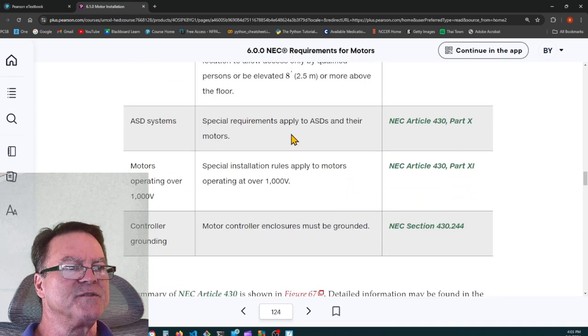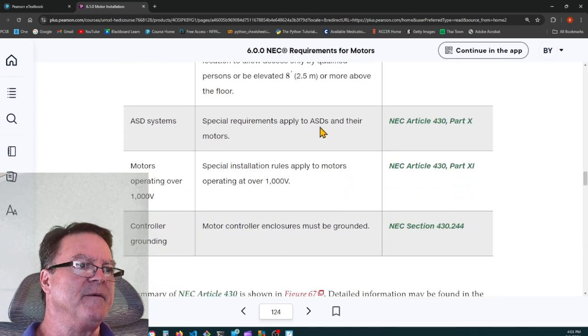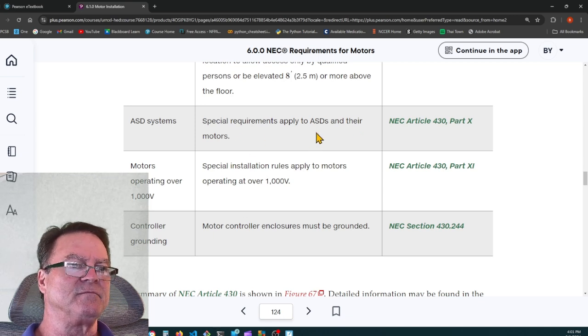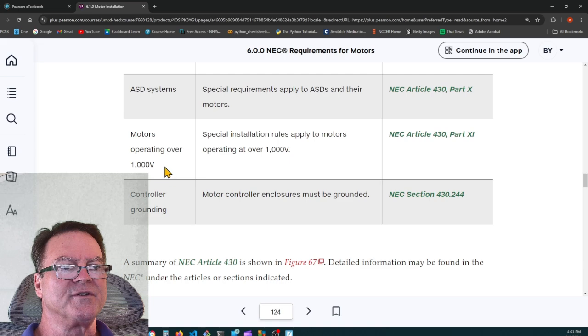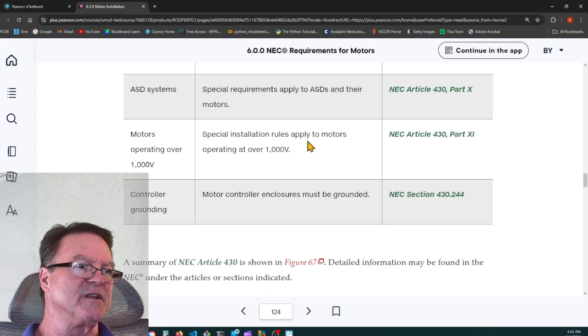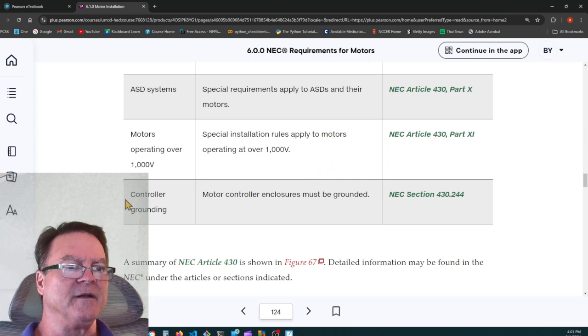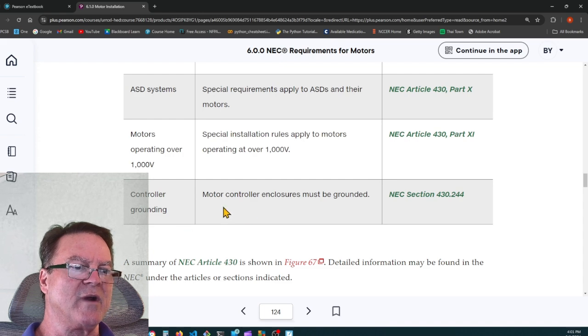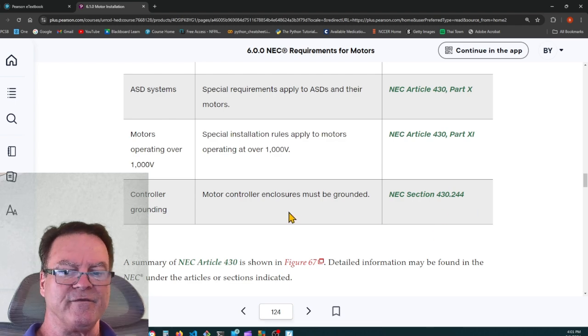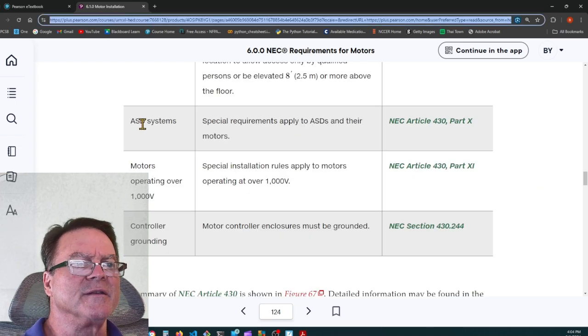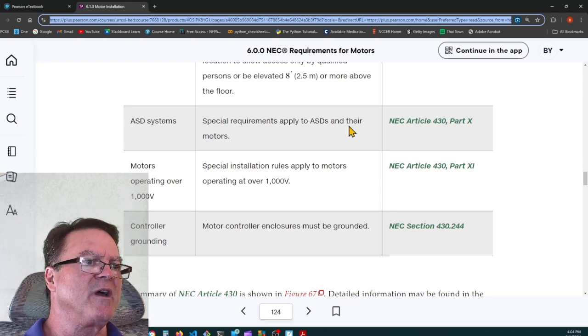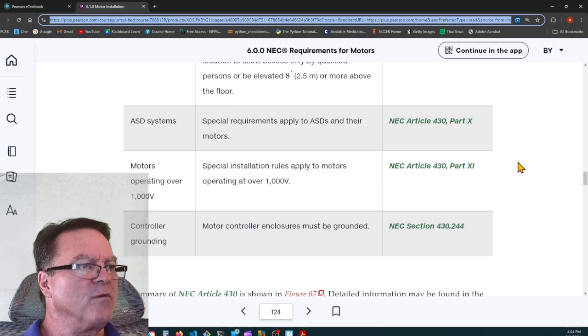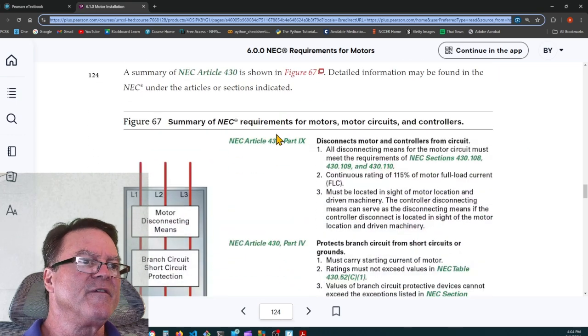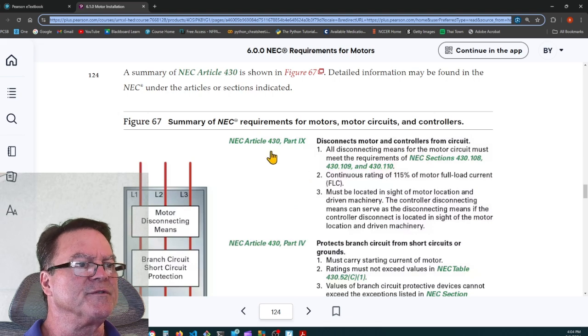above the floor. Special requirements apply to ASDs and their motors. Motors operating over 1000 volts: special installation rules apply to motors operating at over 1000 volts. And controller grounding: motor controller enclosures must be grounded. 430.244. All right, excuse me, yeah, that's adjustable speed drive. Special requirements apply for adjustable speed drives and their motors. That's 430 part 10. Summary of NEC requirements for motors, motor circuits, and controllers.